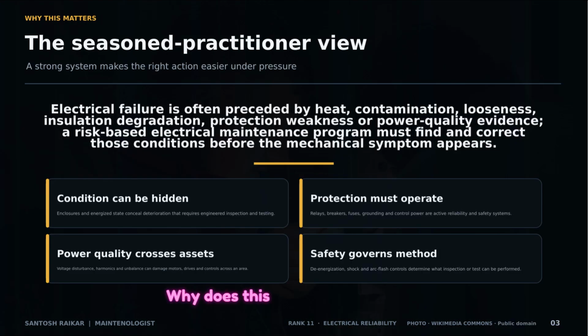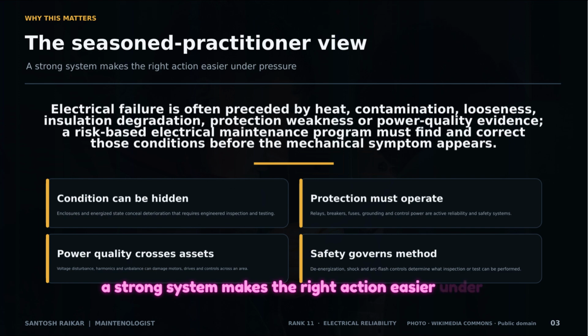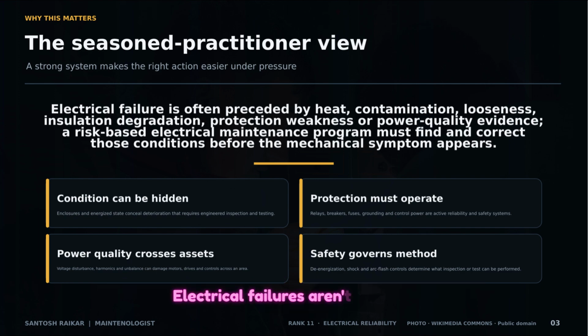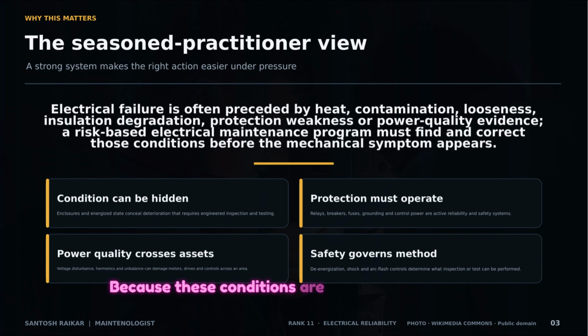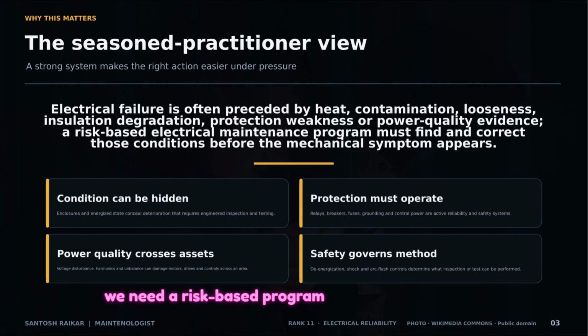Why does this perspective matter? From a seasoned practitioner's view, a strong system makes the right action easier under pressure. Electrical failures aren't random. They're preceded by measurable signals like heat, insulation degradation, or power quality shifts. Because these conditions are often hidden behind enclosures, we need a risk-based program that uses engineered inspection and testing to find them before they manifest as mechanical symptoms.